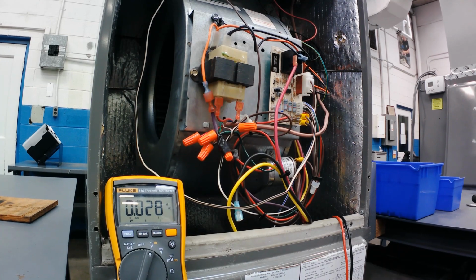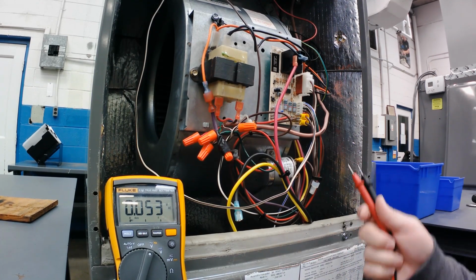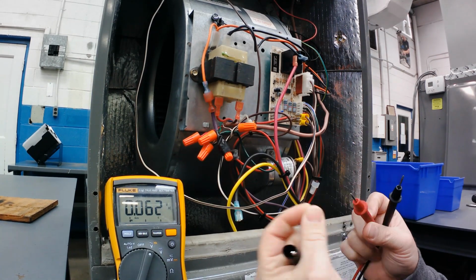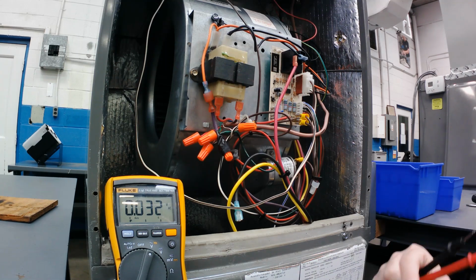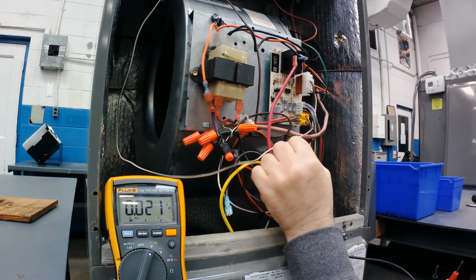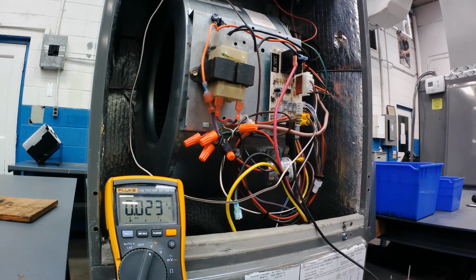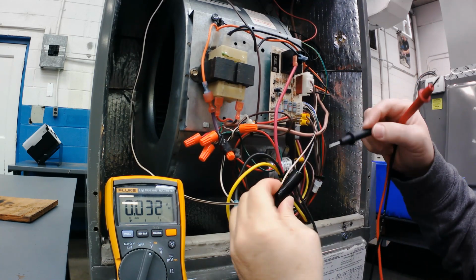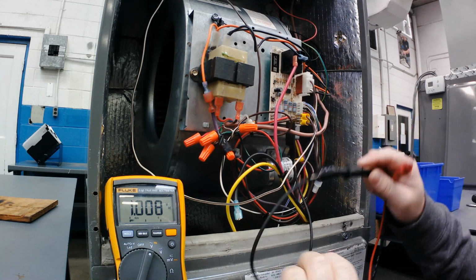All right, here's what I'm going to do. There are test leads that have the screw-on alligator clip with it. I don't have that, so I'm going to do the poor heat and air guy way. I'm going to take an alligator clip and clip right there to my transformer common, and I'm going to put it on the black lead and just lay it out the way.